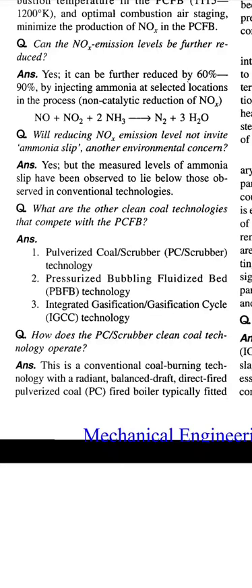Question: How does PC scrubber clean coal technology operate? Answer: This is conventional coal burning technology with a radiant balanced draft direct-fired pulverized coal boiler, typically fitted with a regenerative air heater, a selective catalytic reduction (SCR) reactor for NOx control, a wet limestone forced oxidation spray tower flue gas desulfurization system for SO₂ control, and a baghouse for particulate control. One such process is schematically presented in the figure. All of the coal fired is used to generate steam, which is utilized in a conventional Rankine steam turbine cycle.